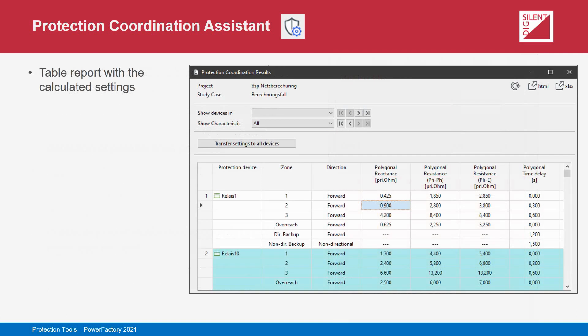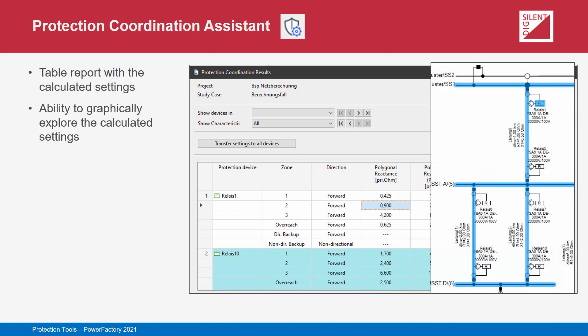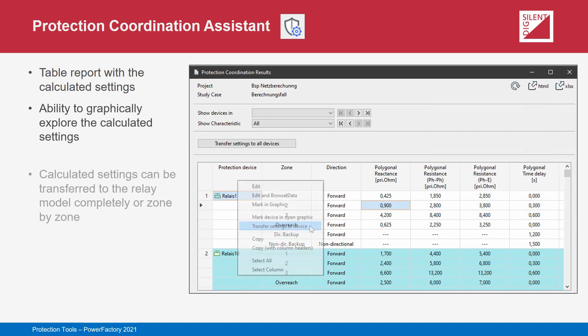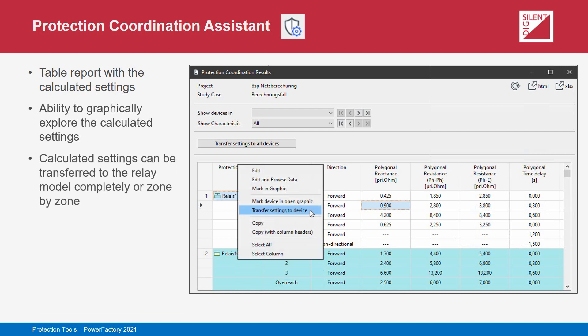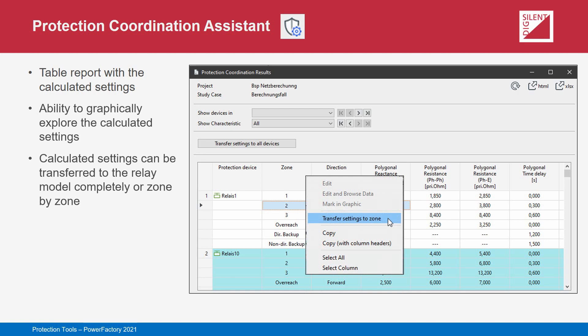Once settings have been calculated, the results can be viewed in a tabular report showing the calculated reach for each zone of each coordinated relay along with the associated time delays. Both polygonal and circular zone reaches can be displayed. The tabular report is interactive — it is possible to use the report to find relays in the single line diagram or to mark the elements involved in the calculation of a zone. Once satisfied with the settings, the user can transfer them to the relays directly from the report, on a per zone, per relay, or all-relay basis.